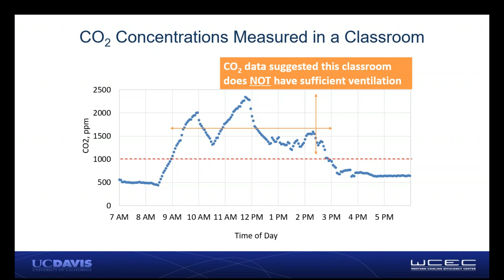This is one example of data we measured in an ongoing project I'm working on with Teresa, where we have low concentration in the classroom before the kids arrived. Throughout the day, as the kids arrived and went to lunch and on break, you can see how CO2 concentration tracks with occupancy. In this particular case, we see concentration above the 1,000 ppm level, an indication that this classroom does not have enough ventilation. We also look at the duration of the exceedance—for this classroom, there's a long period exceeding 1,000 ppm, another indication of insufficient ventilation. So measuring CO2 is a convenient way to estimate ventilation rate in a classroom.